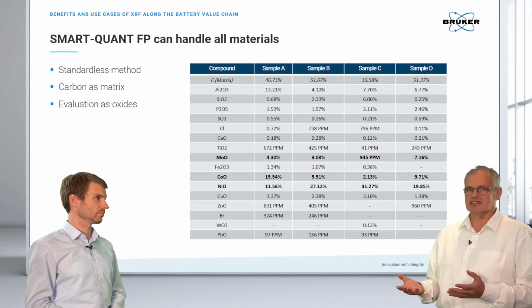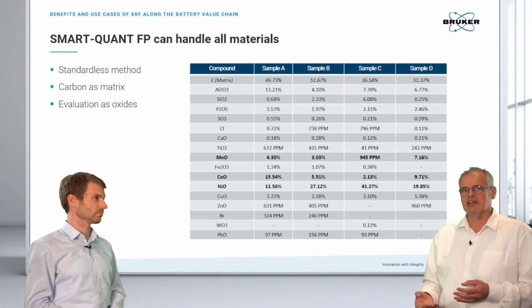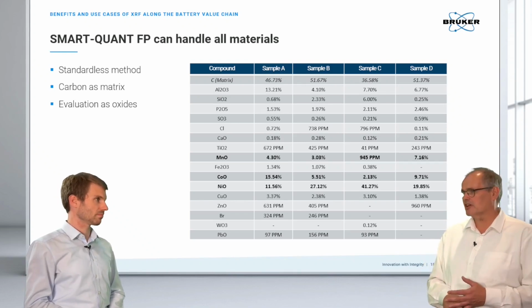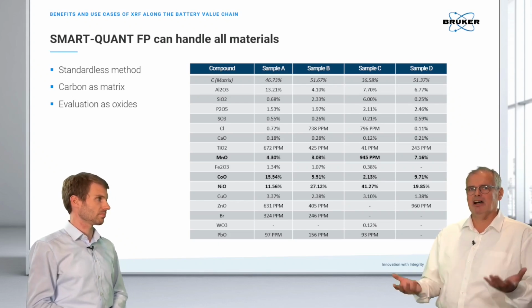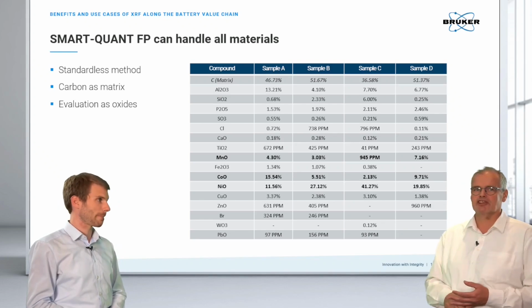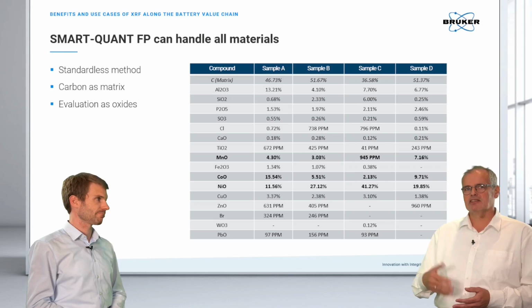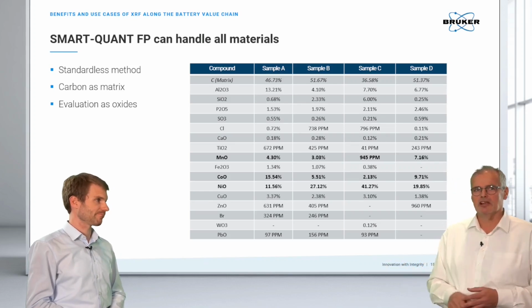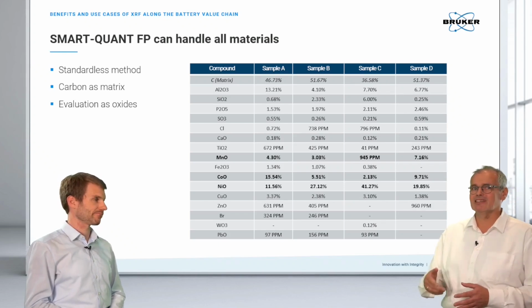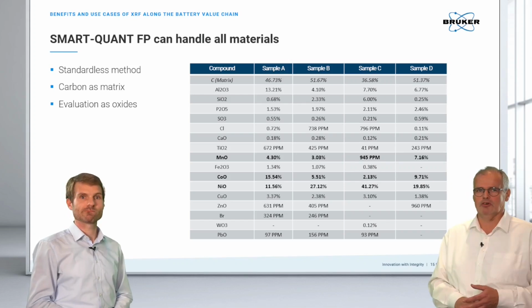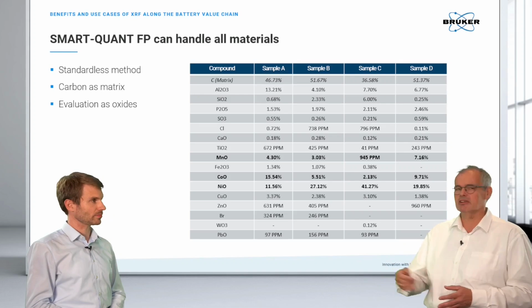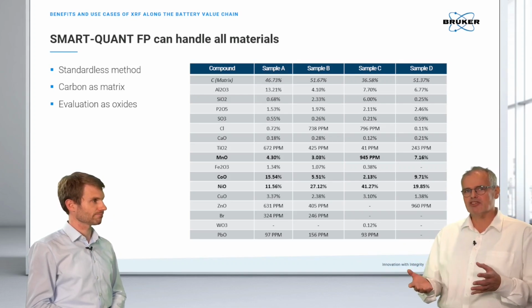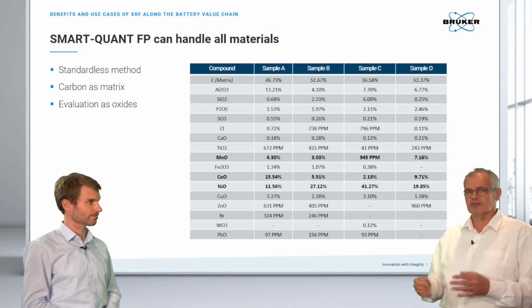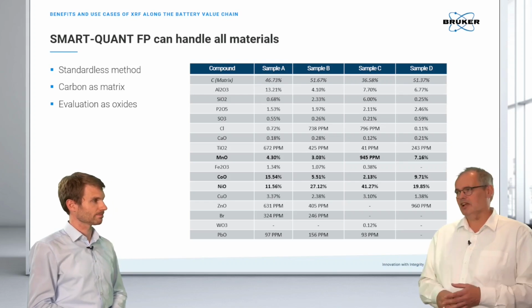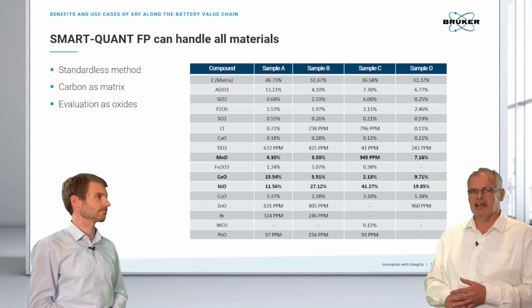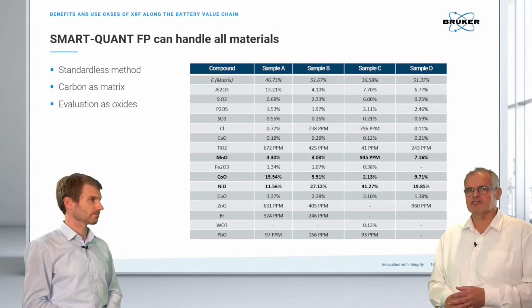Nevertheless, in a recycling process, there's always a way of contamination. There will be some foreign material going inside, some other metal parts which are shredded and suddenly show up in your fraction, the black mass fraction, and suddenly you see some elements which you don't expect, like titanium. The good thing using SmartQuant FP is then that the titanium will be evaluated and show up as a data point. So you would see, hey, I have a contamination in my material. And so this is especially important for people who are buying black mass for further refinement. Means it's easier for the primary supplier because he might know exactly the battery cell type, and therefore he can react and better sort the material.